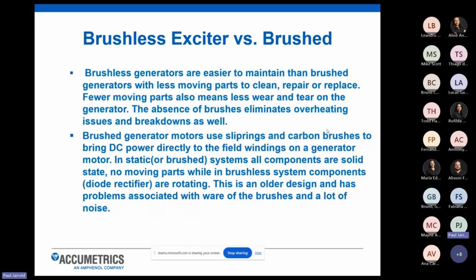In a brushed exciter, you have direct access to the DC field. That's brought across some static brush systems, so it's a mechanical contact to bring DC power to the generator rotor itself. On a brushless system, you don't have direct access to the DC field, so it's different from the brushed unit. Our focus at Accumetrics is supporting the brushless exciter market, both for end users and machines that are installed in the field, as well as new machines being built at the factory level.